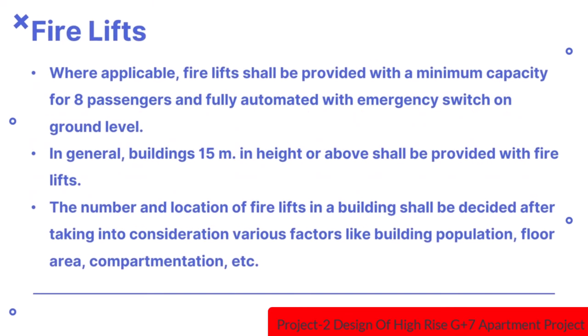Where applicable, fire lifts shall be provided with a minimum capacity for 8 passengers and fully automated with emergency switch on ground level. In general, buildings 15m in height or above shall be provided with fire lifts. In case of fire, only firemen shall operate the fire lift; in normal course, it may be used by other persons.